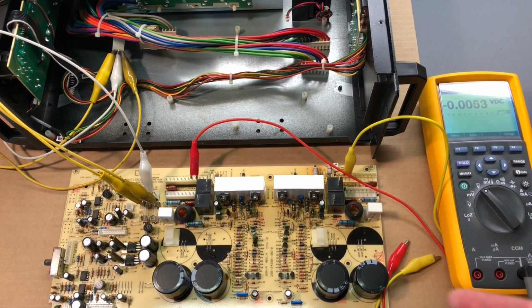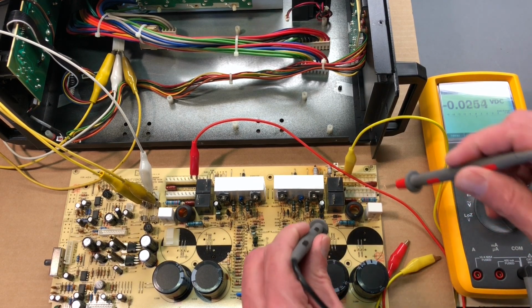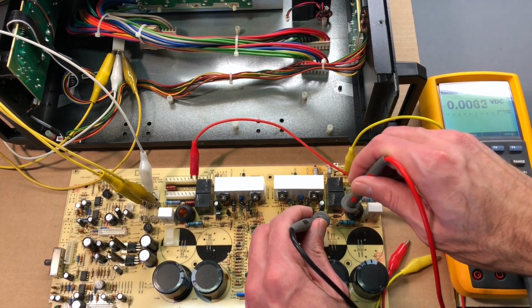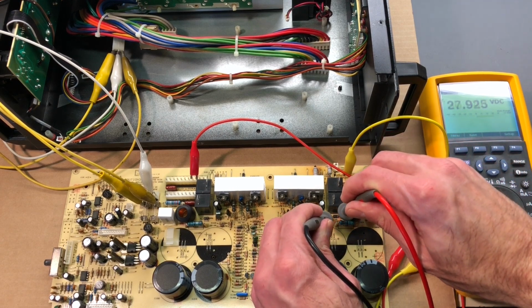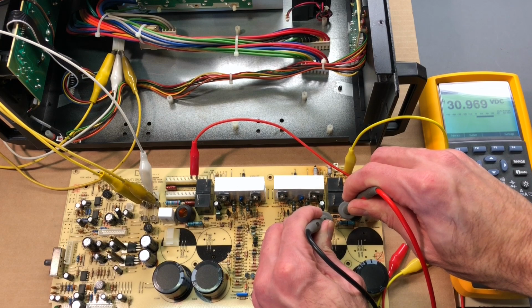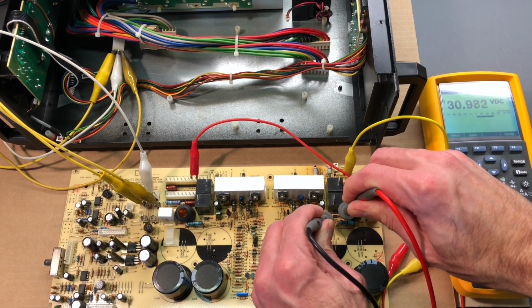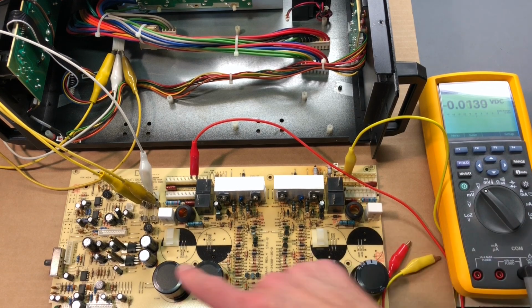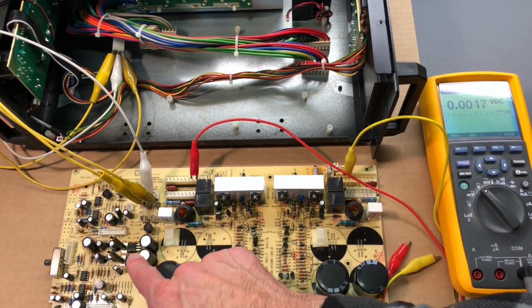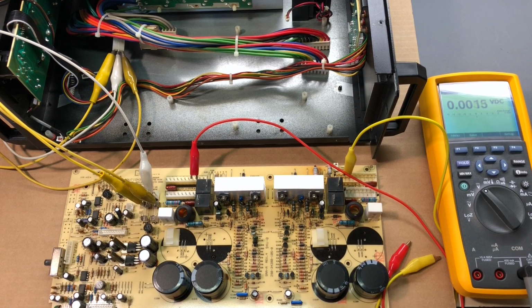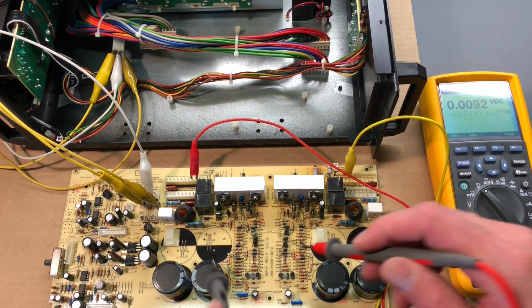Because those diodes are directly across the coil, we can actually measure that coil voltage. Let's see what we have on this one here. Yeah, 30 volts, almost 31. That's what I was thinking - those aren't powered through the voltage regulators, the 15 volt plus and minus regulators over here. It's interesting though, they're powering this with 31 volts and they're 24 volt relays, so a little bit on the high side, but not much could be done about that.